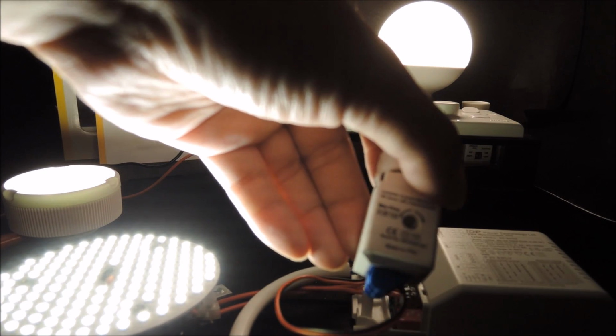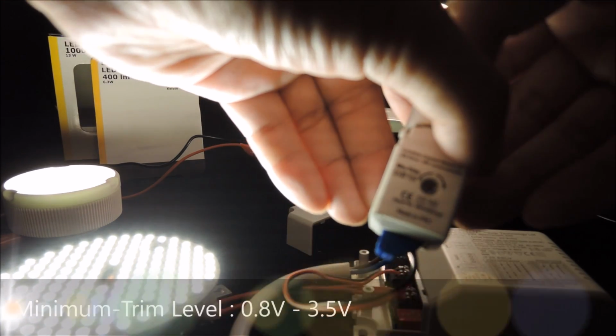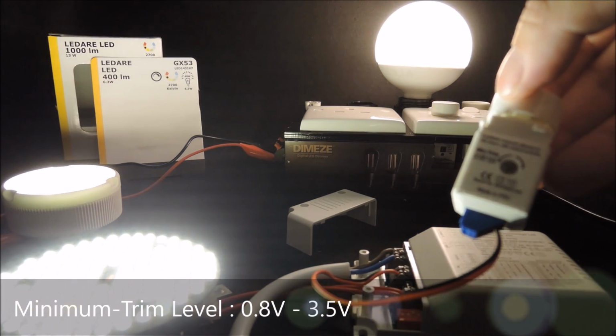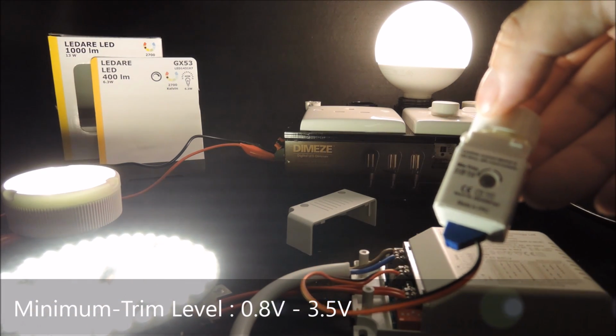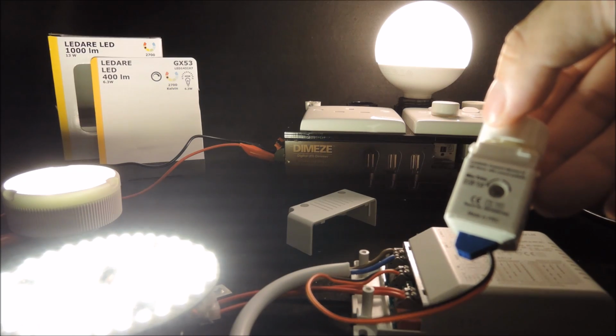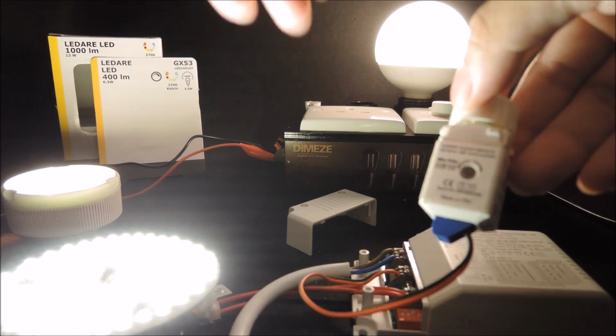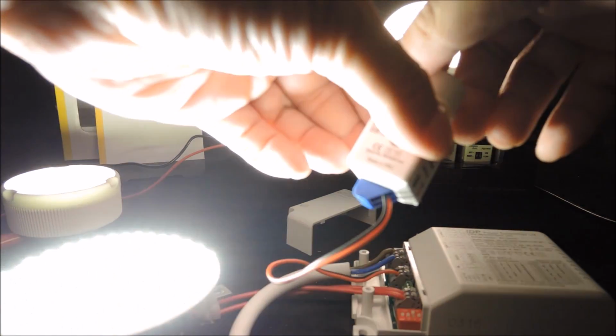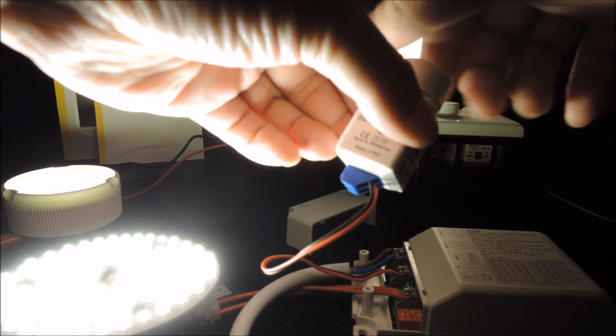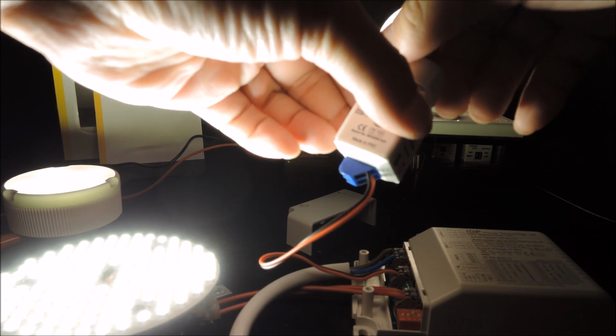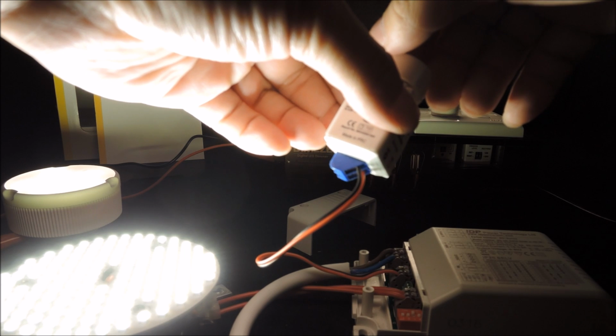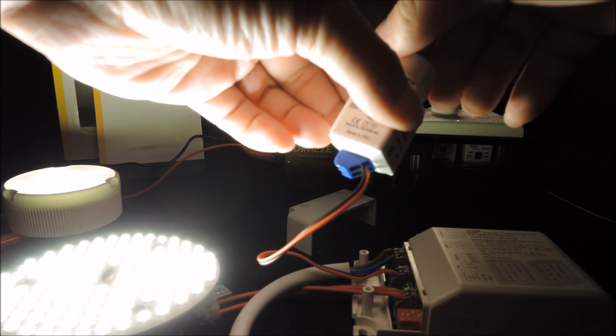For our device, the minimum trim option can set the minimum level from 0.8 volt to 3.5 volt. In other words, once set, the dimming range would be from the minimum to 10 volt. For example, if we set the level to be 3 volt, we may dim the lamp to approximately 1/3 of the maximum brightness level.